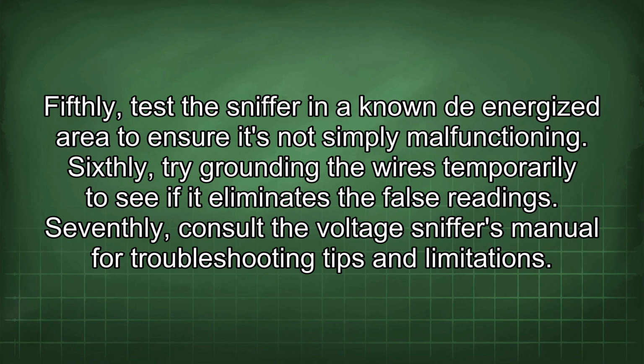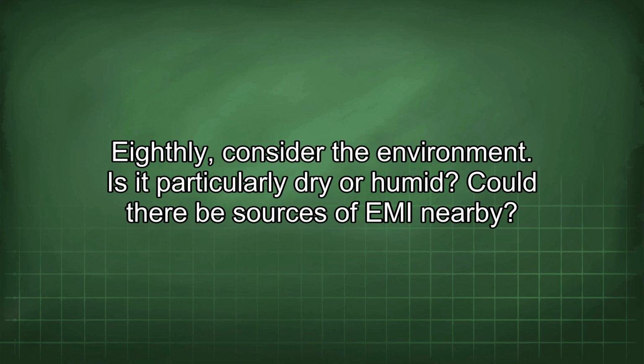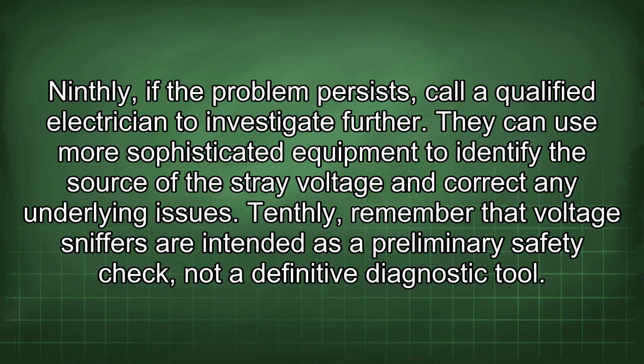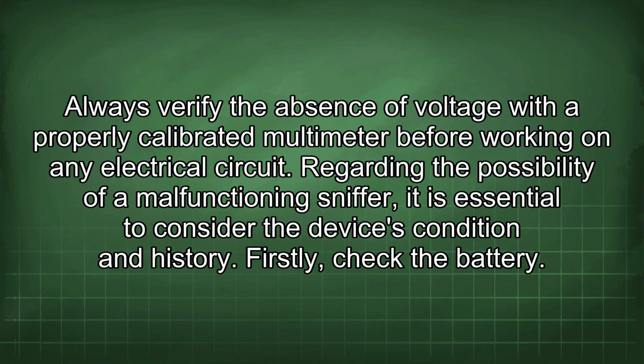Fifthly, test the sniffer in a known de-energized area to ensure it's not simply malfunctioning. Sixthly, try grounding the wires temporarily to see if it eliminates the false readings. Seventhly, consult the voltage sniffer's manual for troubleshooting tips and limitations. Eighthly, consider the environment. Is it particularly dry or humid? Could there be sources of EMI nearby? Ninthly, if the problem persists, call a qualified electrician to investigate further. They can use more sophisticated equipment to identify the source of the stray voltage and correct any underlying issues. Tenthly, remember that voltage sniffers are intended as a preliminary safety check, not a definitive diagnostic tool. Always verify the absence of voltage with a properly calibrated multimeter before working on any electrical circuit.